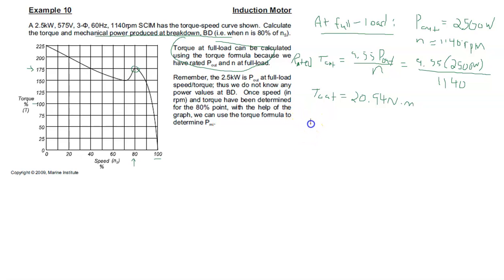We know N is 1140 RPMs. We know that N is less than Ns, and we know that Ns is 120 f divided by p. So there's an inequality we can write: N is less than 120 f divided by p. That allows us to say that p is less than 120 times f divided by N.